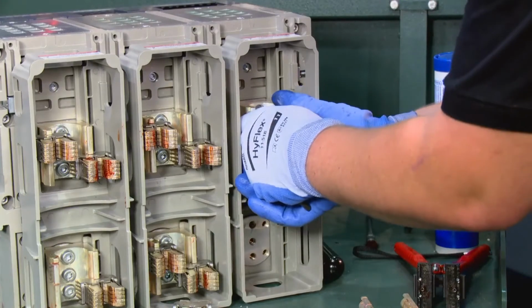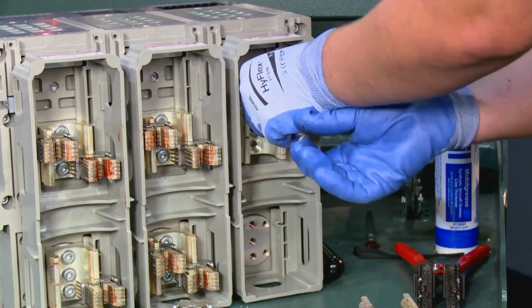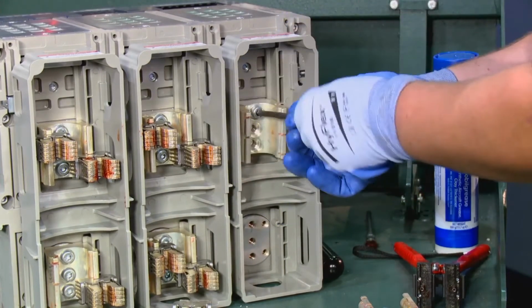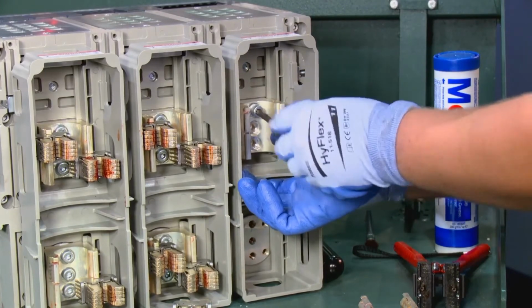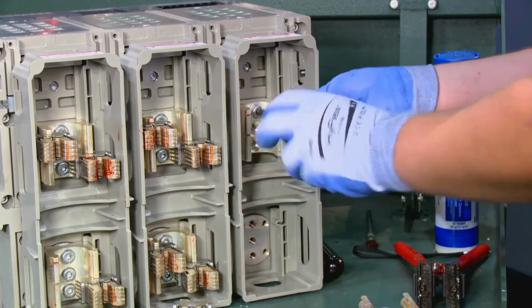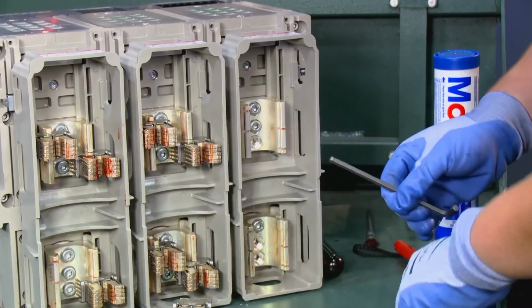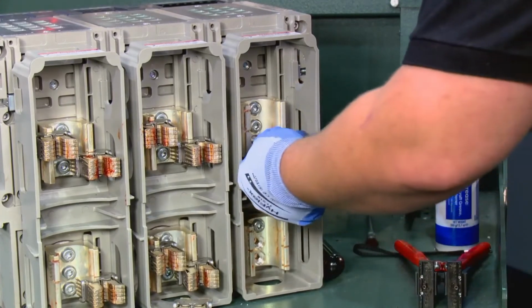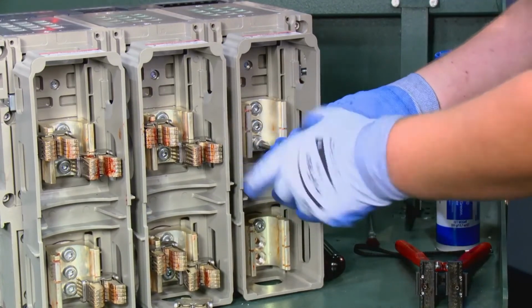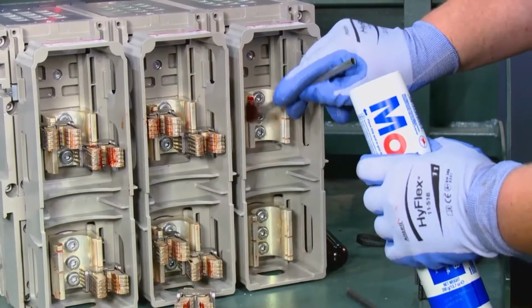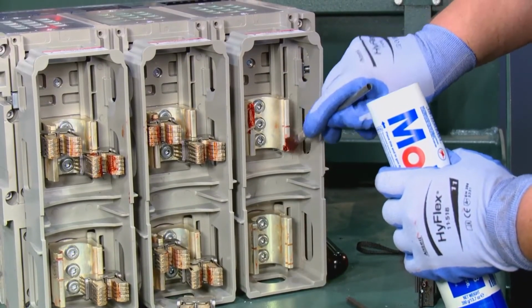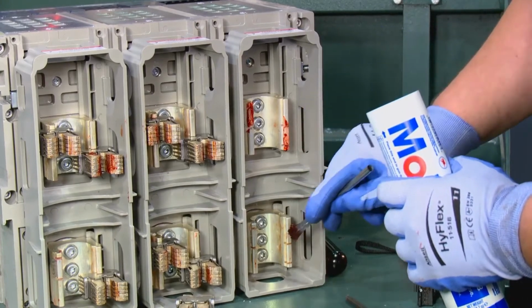Align the cluster shields and cluster supports on the back of the Masterpact breaker and hand tighten the mounting screws with washers. There should be 8 or 3 mounting screws depending upon the type of breaker, cluster shields, and cluster supports required. Make sure you hold the cluster supports vertical by the shield like Brooks is doing when torquing the screws. Apply grease to the cluster supports and to the clusters.